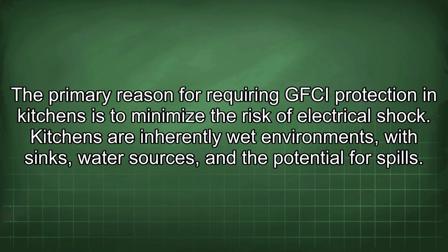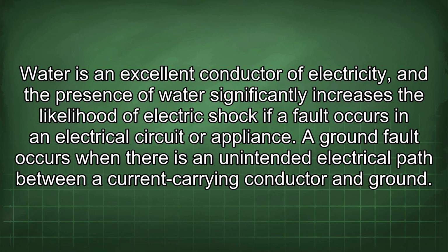The primary reason for requiring GFCI protection in kitchens is to minimize the risk of electrical shock. Kitchens are inherently wet environments with sinks, water sources, and the potential for spills. Water is an excellent conductor of electricity, and the presence of water significantly increases the likelihood of electric shock if a fault occurs in an electrical circuit or appliance.